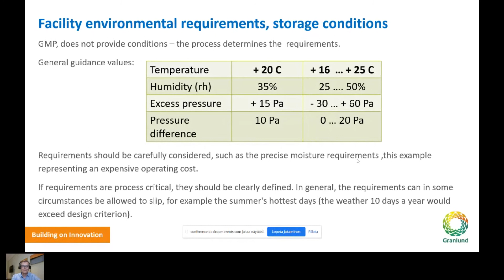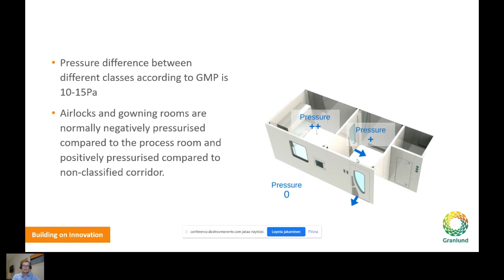Pressure differences in different classes according to GMPs are normally 10 to 15 Pascal, and airlocks and gowning rooms are normally negatively pressured compared to process rooms, and positively pressured compared to non-classified corridors. But if there are some hazardous processes, then the process rooms must be negatively pressurized to surrounding areas, and those are then quite difficult to design so that all pressures between different areas are handled correctly.